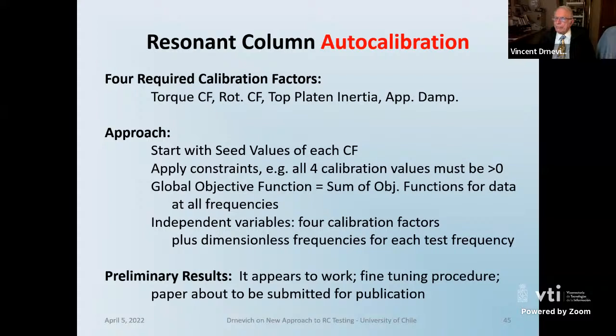But we said to ourselves, if we need the torque calibration factor, rotation calibration factor, top plate inertia, and apparatus damping, what happens if we put a calibration rod in place where the shear modulus, damping, and inertia are known? And so we did this, and then we applied this frequency sweep process. So we can get 200 data points where we know the shear modulus and damping, and we know the stiffness. What we then do is use the torque calibration factor, the rotation calibration factor, the top plate inertia, and apparatus damping as unknowns or dependent parameters, with the measured values as the independent parameters.